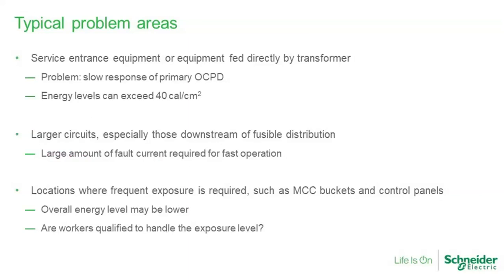Maybe service entrance equipment or any equipment fed directly by a transformer. The problem there might be a slow response of a primary protective device, so the energy levels can get up to those certainly well above 1.2 calories, in some cases maybe even above the 40-calorie level, and that tells us that we need to do something about what we're looking at there. Similar problems can appear on any larger circuits, especially those downstream of fusible distribution. But to be fair, you can have problems downstream of large circuit breakers as well, depending on how they are set up and configured.